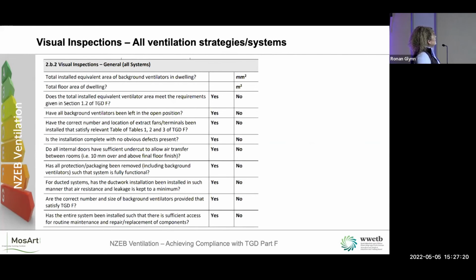So I ask you a couple of questions. So what are the equivalent areas? It's a total installed equivalent area of background ventilators in the dwelling. So does it match up to what the design flow calculations were? What's the total floor area of the dwelling? So you need to know that as well. So you have to look at section 1.2 of Part F. Does the installed equivalent background ventilator meet the requirements?